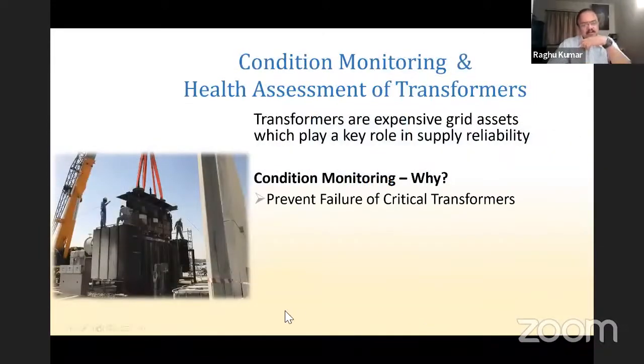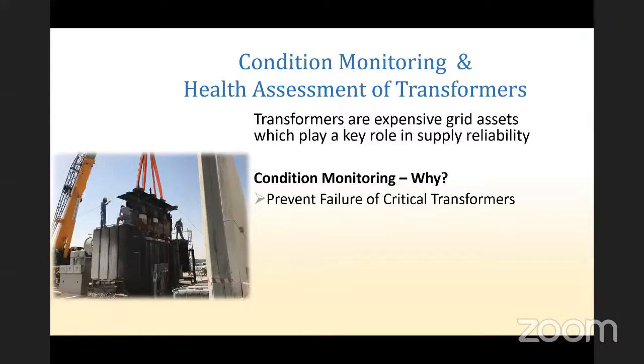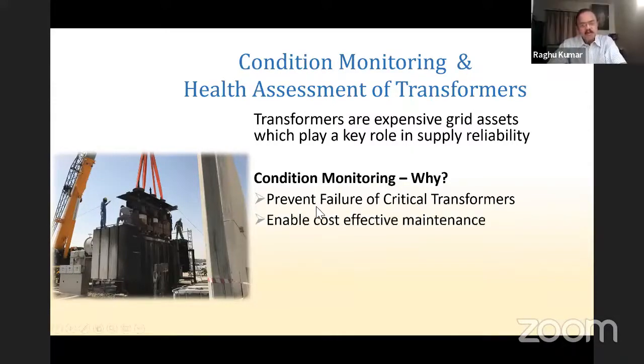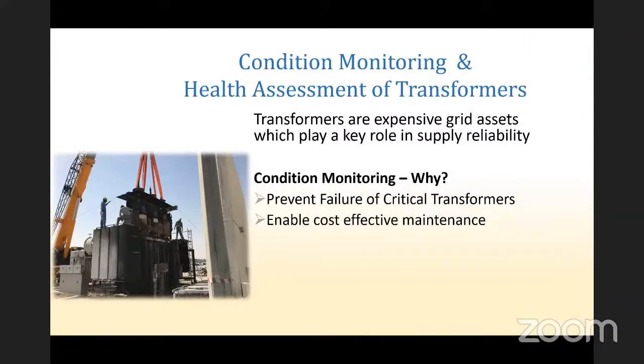This transformer is a failed transformer, and nobody wants to see a transformer in this condition. The windings are being lifted up to understand what went wrong. So now the question is, why is condition monitoring required? Condition monitoring is carried out to prevent failure of critical transformers. And the maintenance has to be made cost effective. You cannot have a very expensive maintenance procedure. So cost effective maintenance is what is required.